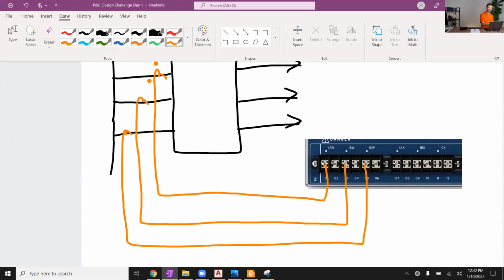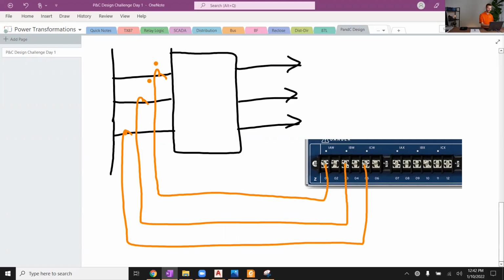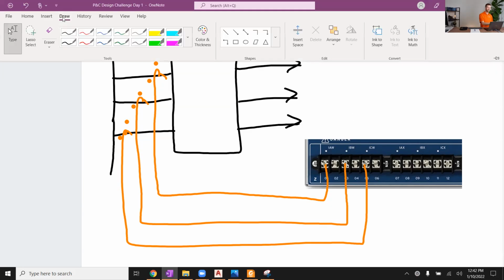Again, we should always draw our polarity dots. I'm reinforcing and saying this over and over again because when you go to do these in CAD, you want to make sure that all these polarity dots are properly drawn. And then what about the non-polarity dots on the neutral side of these 3 CTs? What about the non-polarity dots on the neutral side of these relay current inputs? We typically will tie those together or jumper them together.